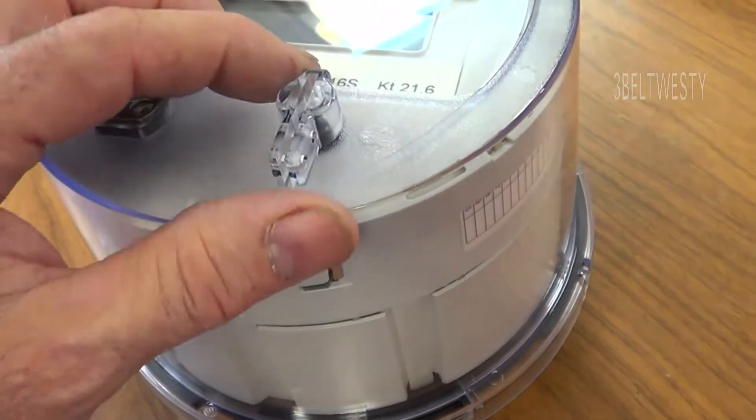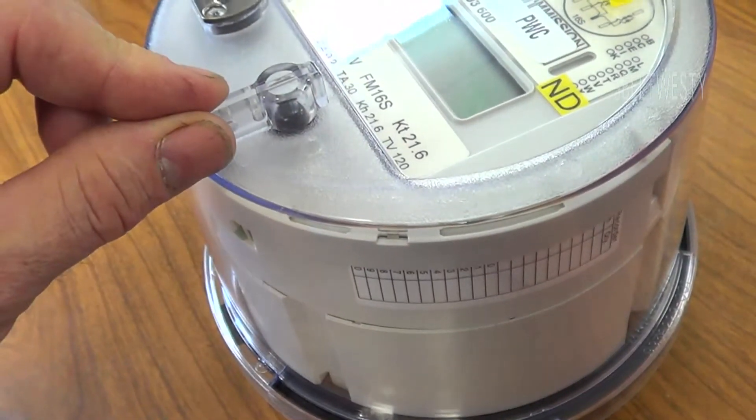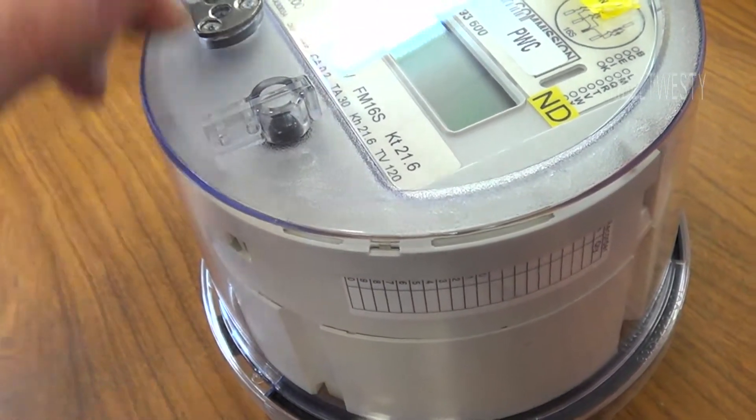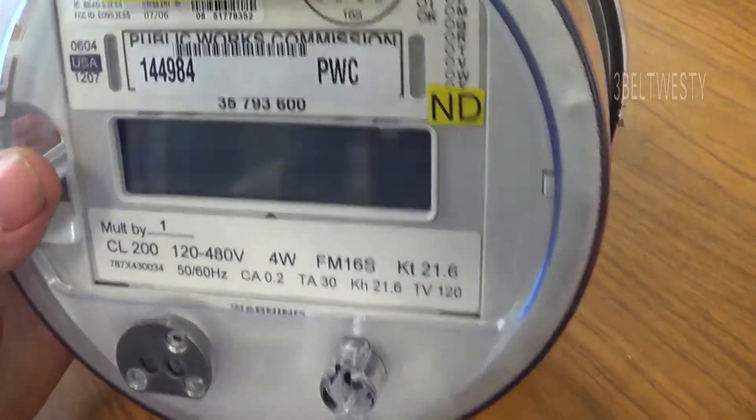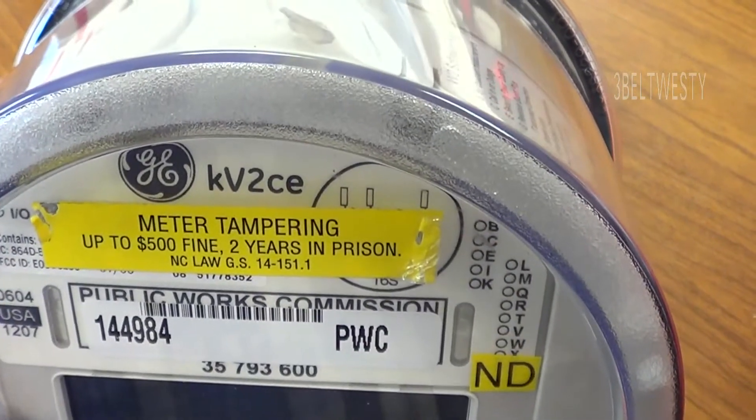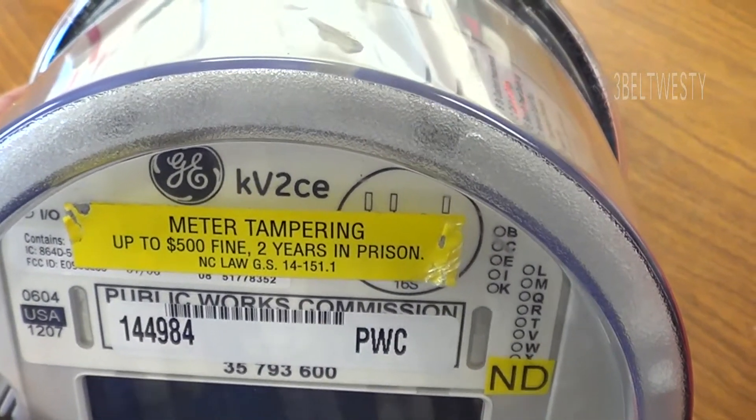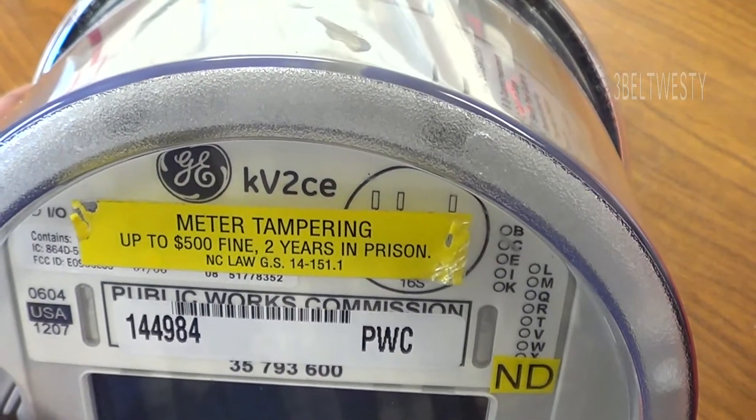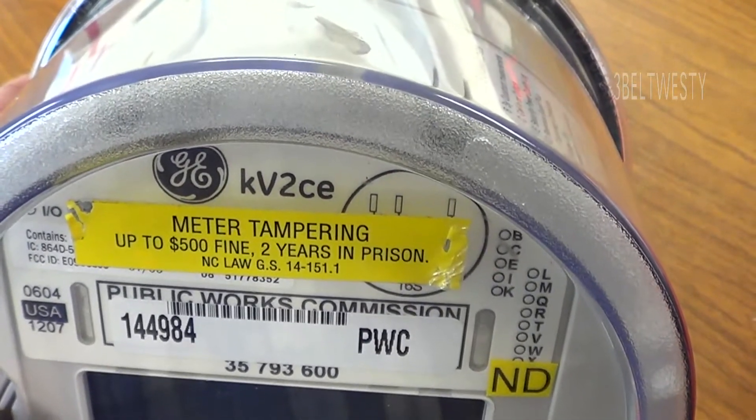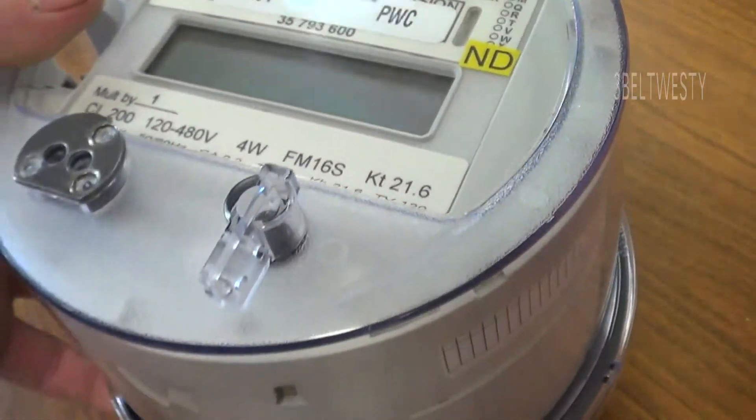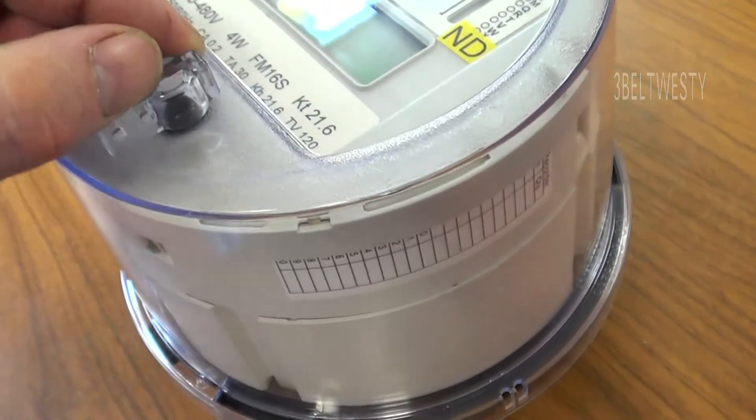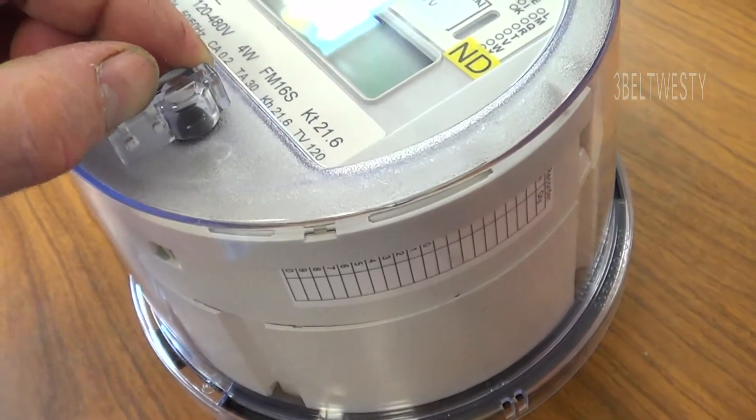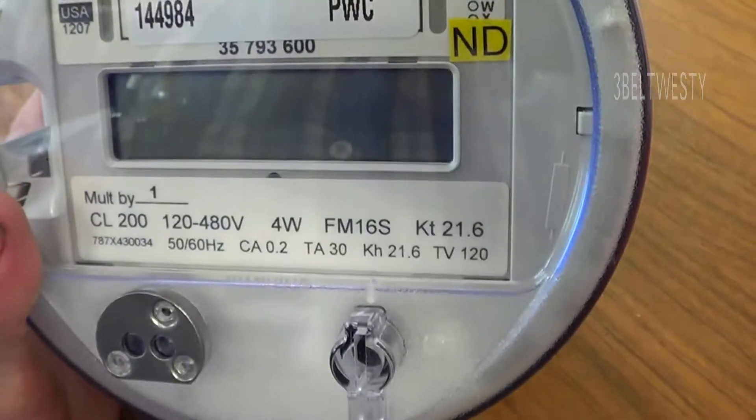This is the optical port. This is the demand reset feature and so the C model does and the KV2 I believe does but the one with the E it's a little bit more obscure model has no demand on it so you can't reset the demand and I don't believe this reads out the demand.